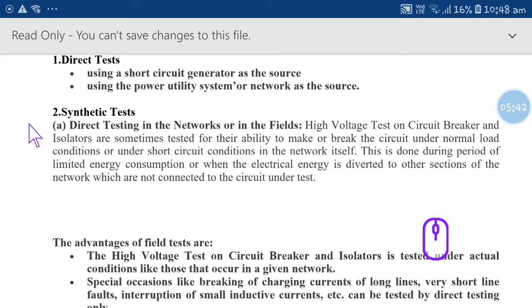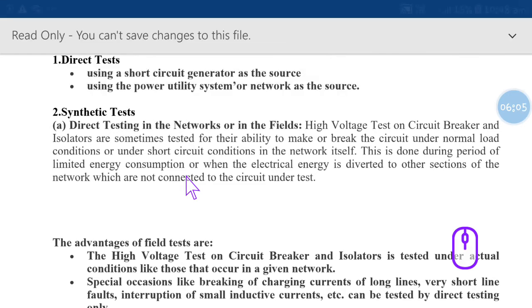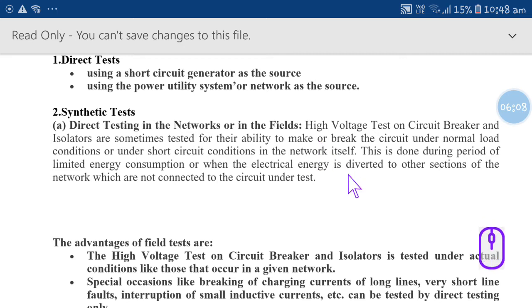What is this here? In direct testing, the high voltage tests on circuit breakers and isolators are tested for make and break, meaning on and off, okay. They do testing under normal load condition, or they can also do it under short circuit condition. In the direct test they do this for a particular period of limited energy consumption, okay. Here the electric energy is diverted to other sections of the network which are not connected to the circuit under test, okay. This type of test is done when electric energy is diverted to the other sections of the network. At that condition, they test free from electric energy, okay.